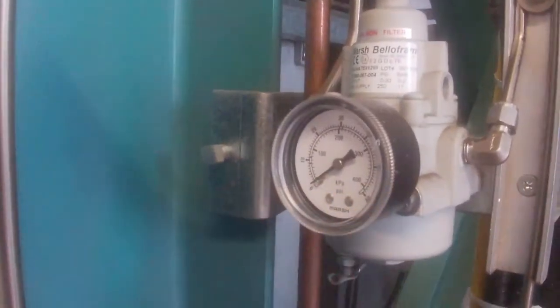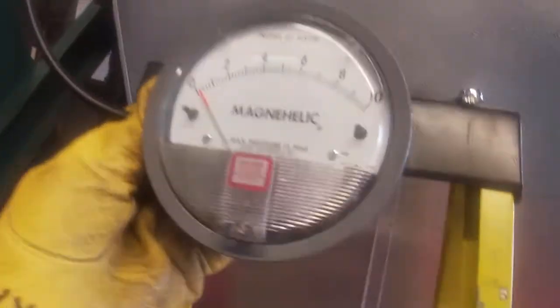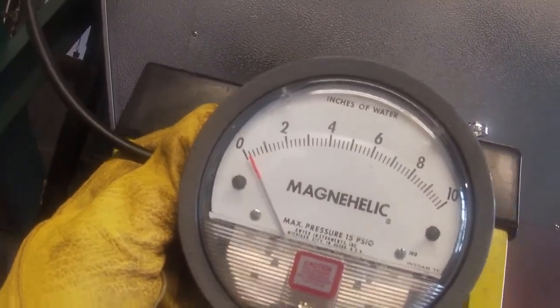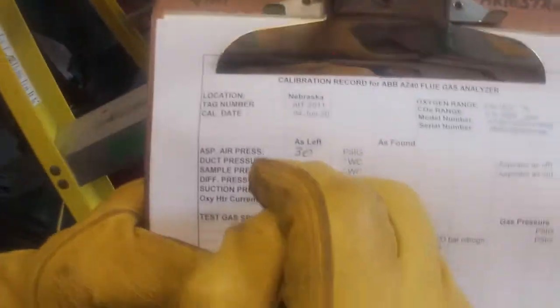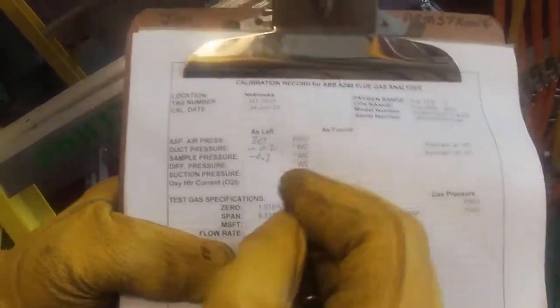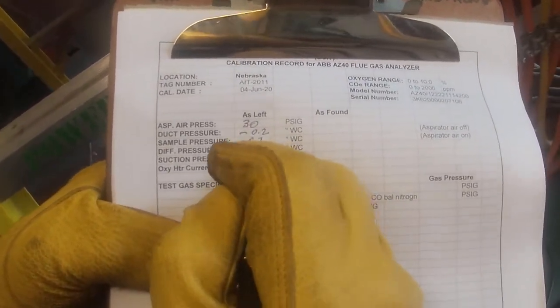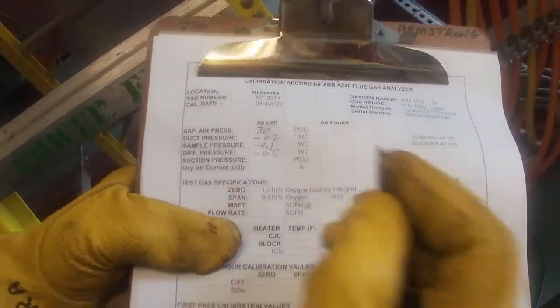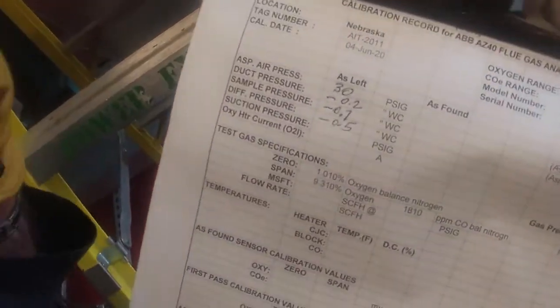Now I'm going to turn the aspirating air off. The air valve is sitting over here on the side. Turn that off. Look at my gauge. Pressure's dropping. It's now at 0. Okay, so the pressure gauge has gone to 0. And if I now look at my draft gauge, it is sitting at minus 0.2. So the differential pressure is minus 0.5. If it's more than 8 inches differential, it means you're plugged up inside. Obviously, this one is really clean right now because it's only looking at 0.5 inches of water column differential.